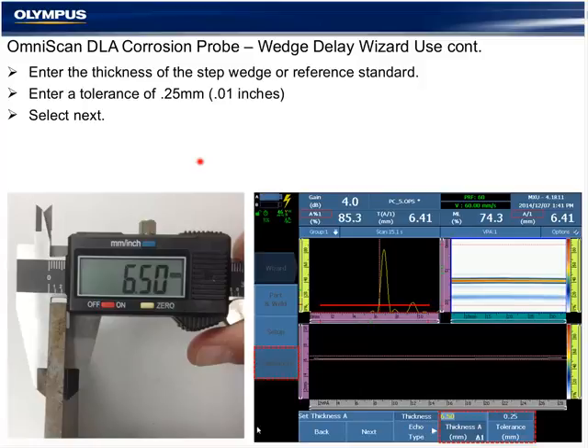If you are using the wedge delay wizard, we want to enter a tolerance of 0.25 millimeters, which is the advertised accuracy of the probe. And again, that 0.25 millimeters is strictly based on us using a leading edge amplitude dependent reading at the gate leading edge position here. The thickness that we're going to use for the wedge delay calibration or validation should either be a reference standard with a certification of known thickness, or more commonly, especially if it's a velocity other than carbon steel, mechanical calipers that we measure ourselves the thickness. We want that to be a precise number, not a nominal thickness.